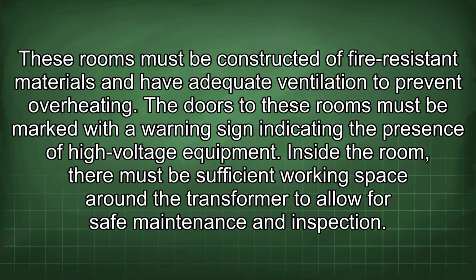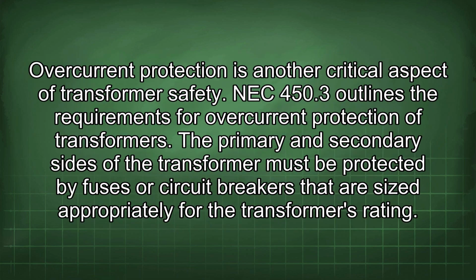These rooms must be constructed of fire-resistant materials and have adequate ventilation to prevent overheating. The doors to these rooms must be marked with a warning sign indicating the presence of high-voltage equipment. Inside the room, there must be sufficient working space around the transformer to allow for safe maintenance and inspection. Overcurrent protection is another critical aspect of transformer safety. NEC 450.3 outlines the requirements for overcurrent protection of transformers.